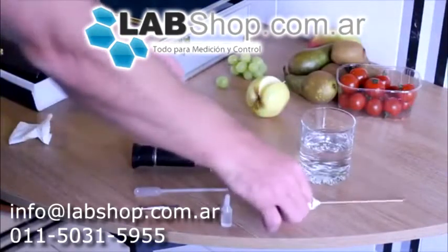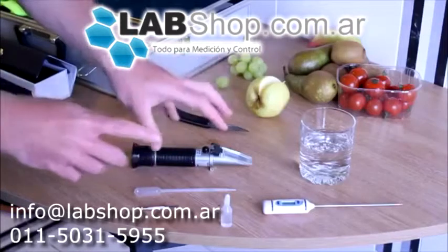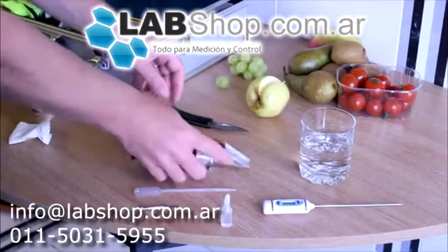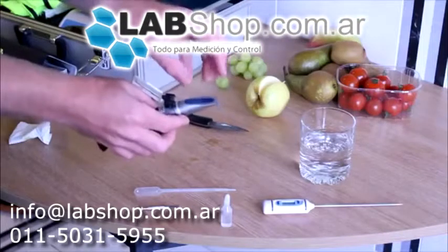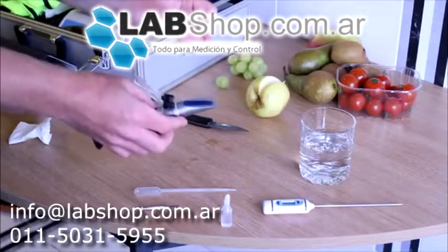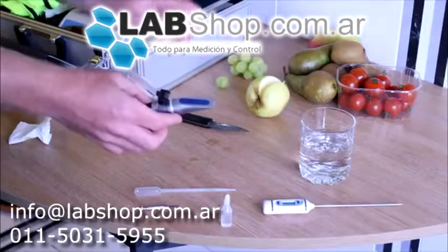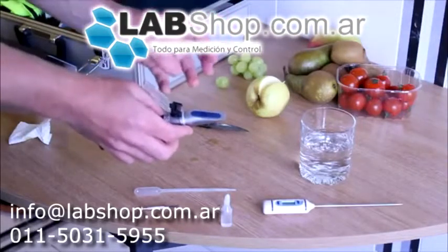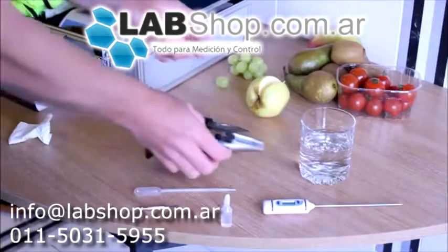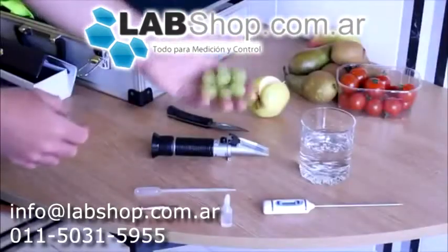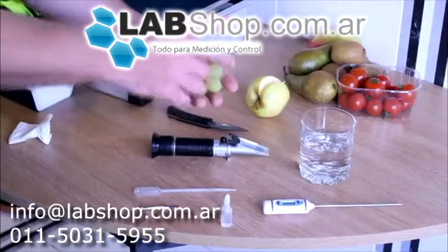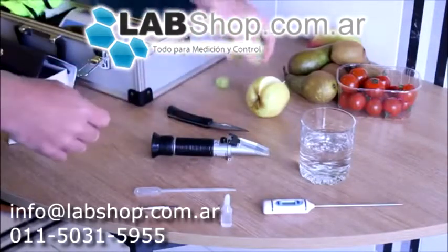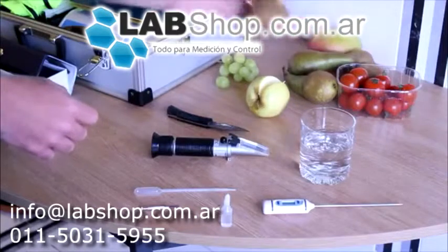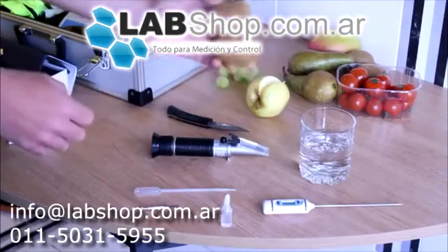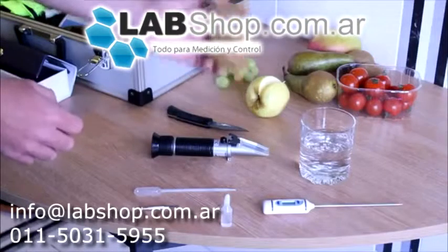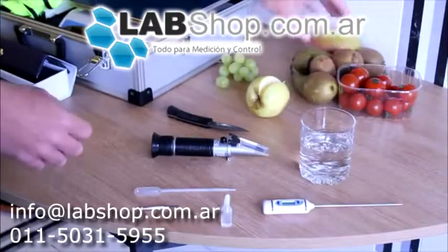A word on temperature, as you may have been used to an adjustment chart for temperature when using a refractometer. The equipment manufacturers now recommend that this equipment be used at 10 degrees and up, and that your sample is the same temperature as your equipment. A significant difference in temperature can result in a reading that is perhaps 0.2 or 0.3 of a percentage out, so it's worth having a probe handy if your samples have been in chill just prior to testing. In terms of selecting your sample, take multiple fruit, whether it be small or larger fruit, and always be careful to discard any products which may show defects likely to affect the readings.